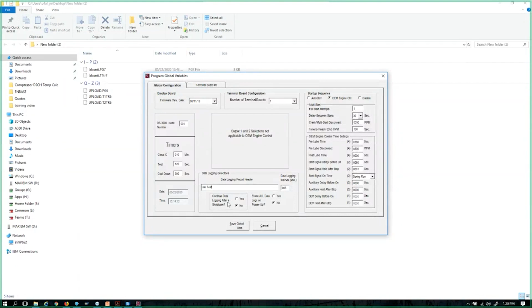Continue data logging after a shutdown. No is the default. We have basically 99 points of data logging intervals that we can store, and we can view that at any time later throughout the system. But once those 99 points are filled, as it brings in a new point, it's going to erase the oldest point. So if we're trying to catch something at a shutdown event, once we're shut down, we don't really want to continue to sit there and record data, because if it's quite a bit of time before somebody gets to the unit to check it out, we could lose what was going on at the time of the shutdown event.